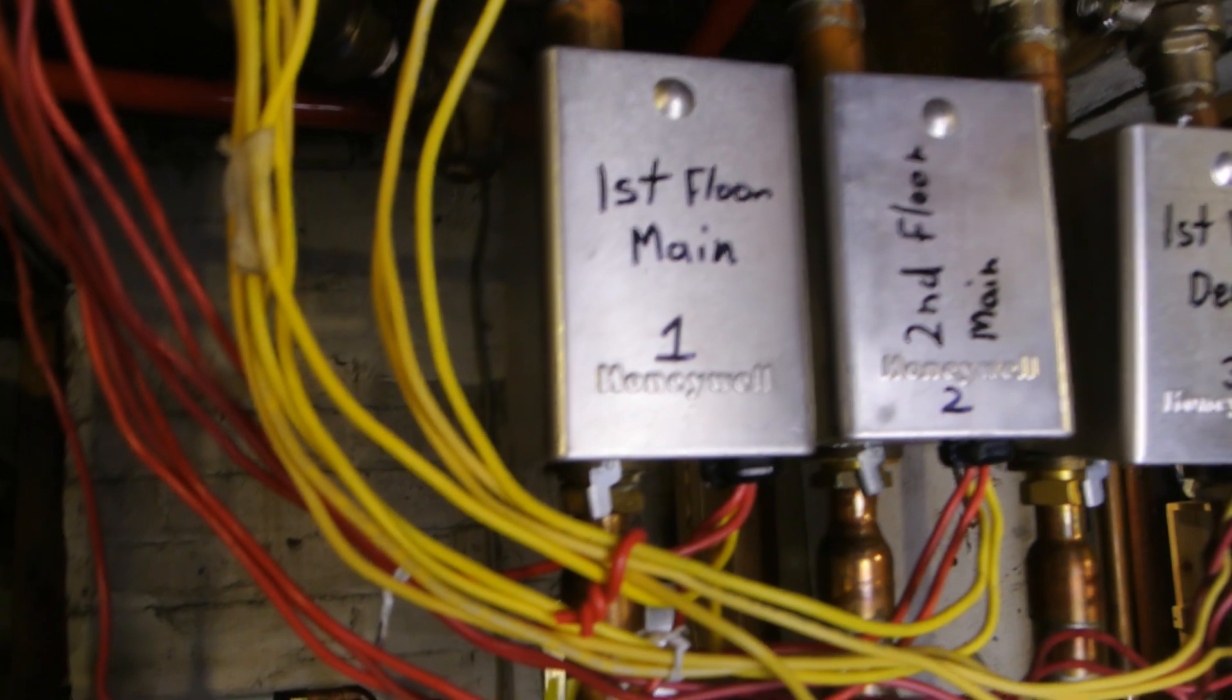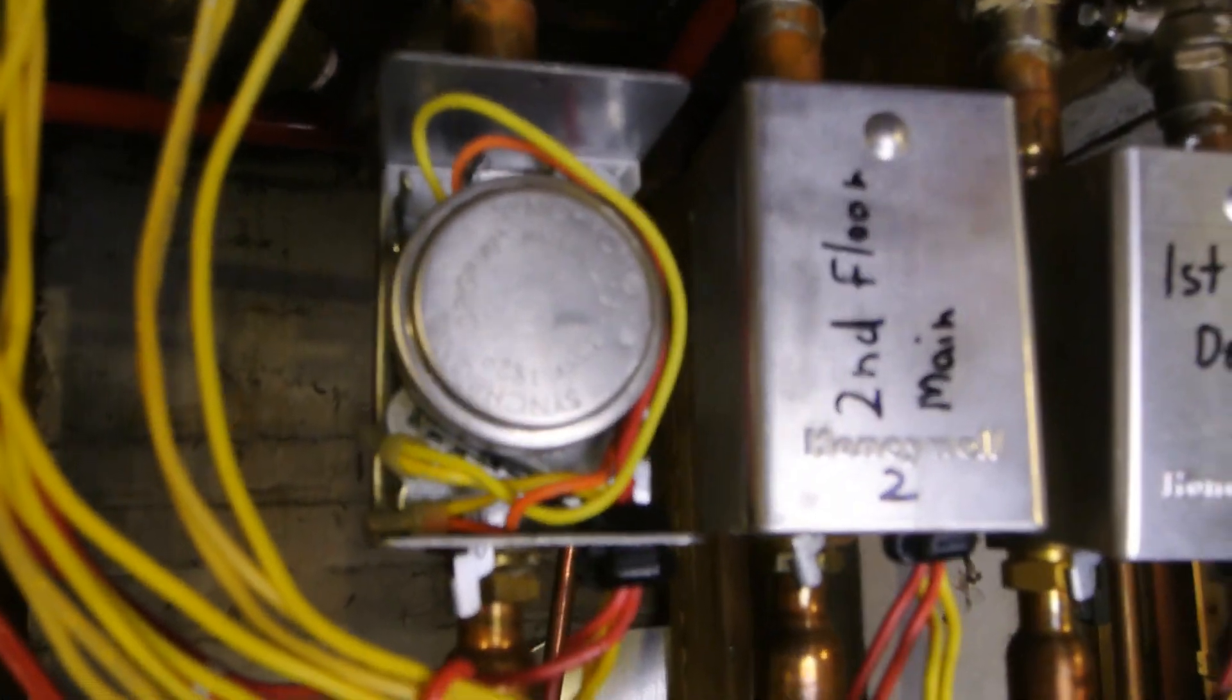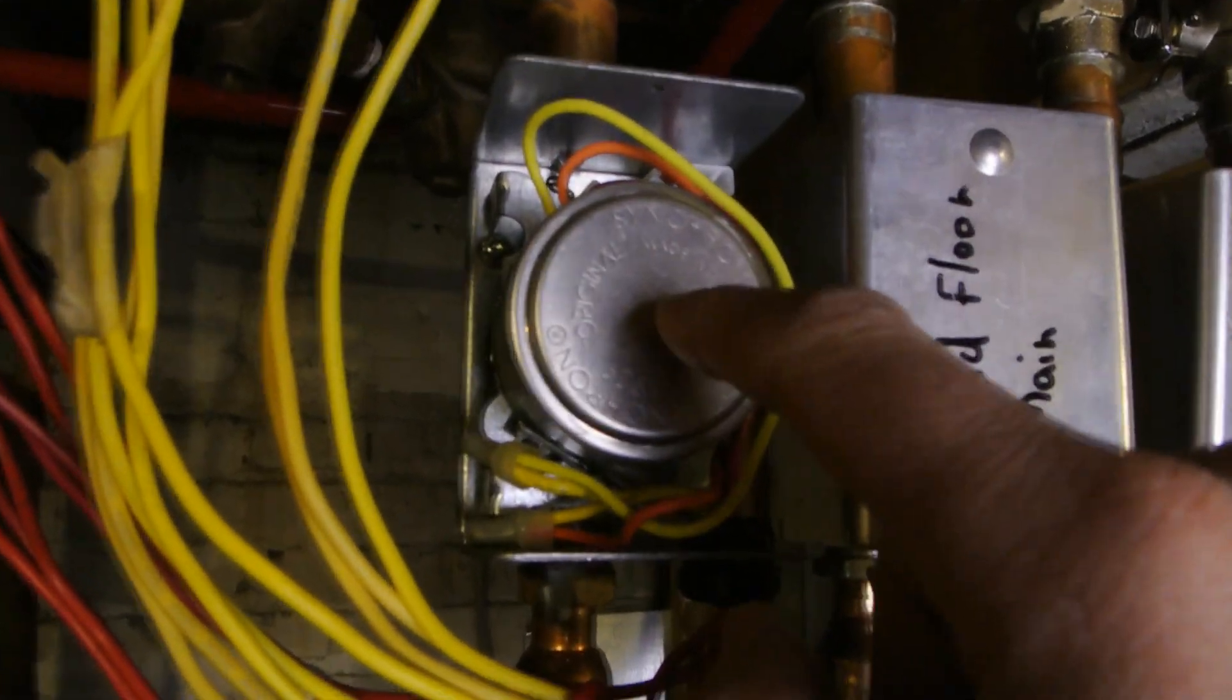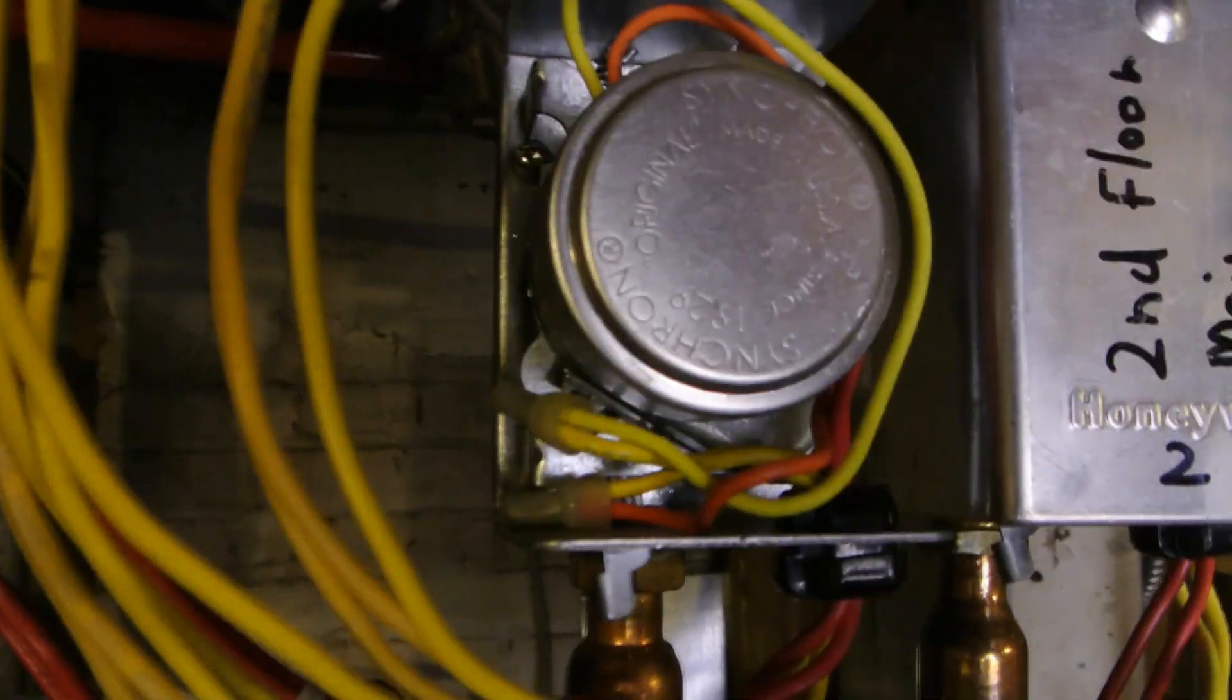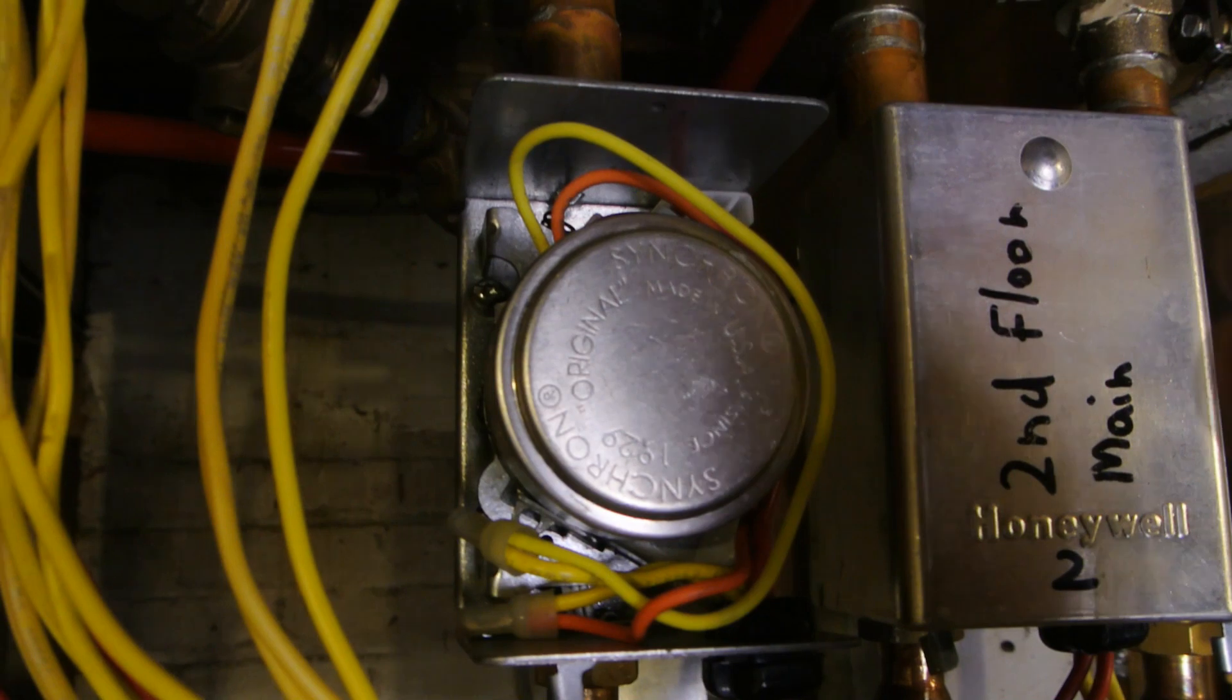It also tells the boiler to turn on, and I'm going to go over the components of how that works. I'm going to take the cover off of this zone valve. It's an electromechanical valve, meaning this is the electrical motor and there's a mechanical portion to it, which is the valve itself. What happens is when you turn on the thermostat, it completes the circuit, causing this motor to turn on and it holds the valve open.